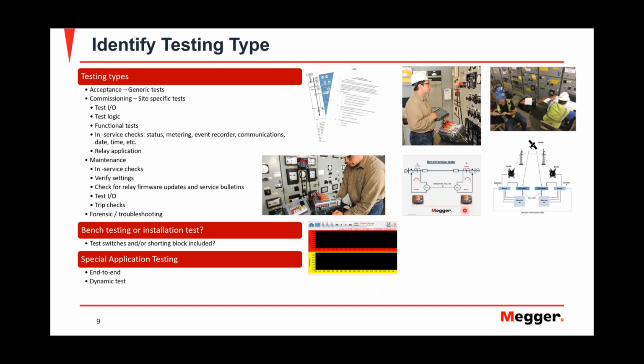Let's say you're doing dynamic test. Dynamic test is when you have a ComTrade file that saves the voltages and your currents into a computer file. You upload that into your relay test set. The relay test set converts that file into actual currents and voltages that you replay them to the relay in order to see its response. So in that case, you need to know, hey, I'm doing dynamic tests. Do I have the file with me? Those are the things that you have to think when you're preparing to go to the site.